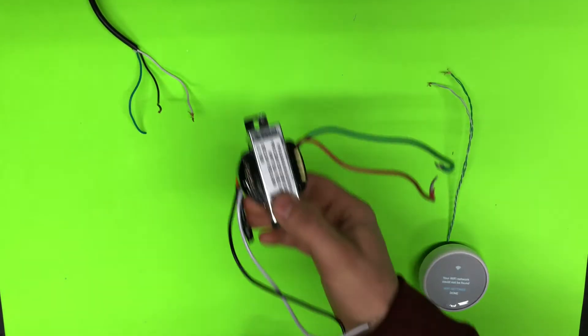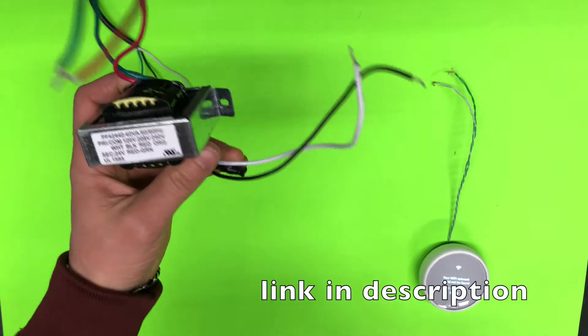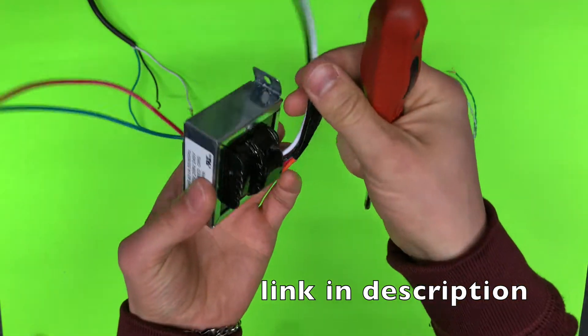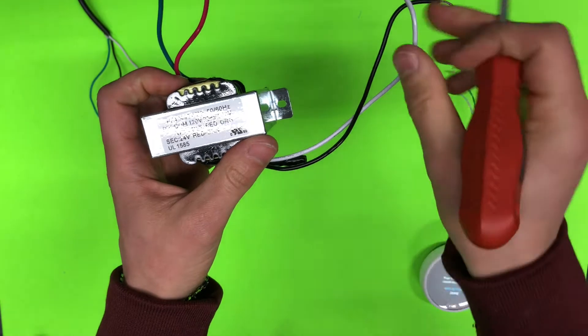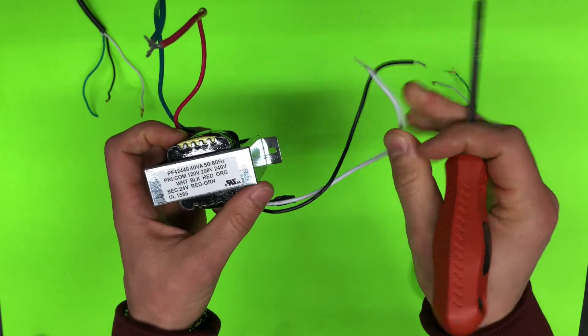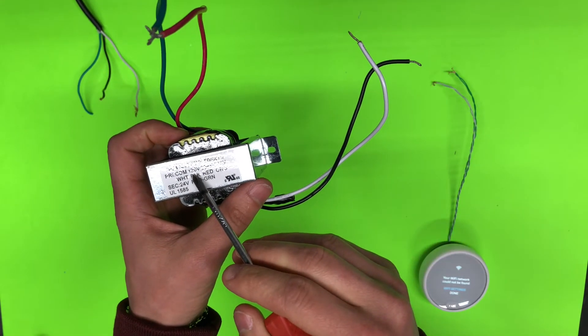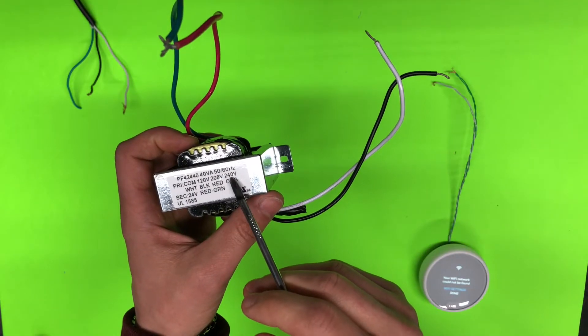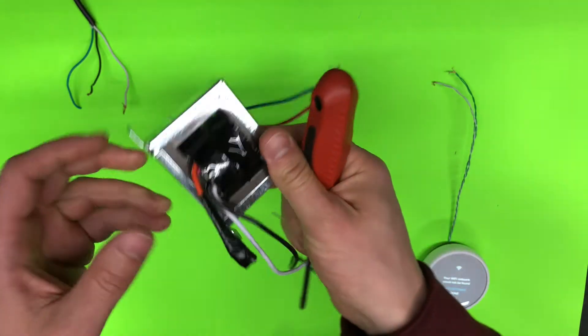So next step, we will need a transformer. In this transformer for input we have four wires. Color code is white is common input, black is for 120 volts, this is what I'm going to use. Red and orange is for 208-240 volts, I'm not going to use it, so I just cut it and isolate this.